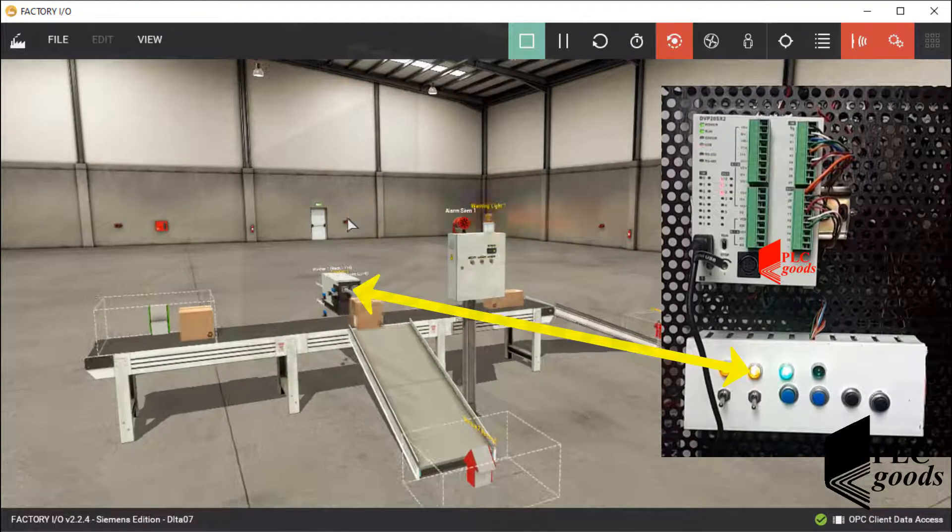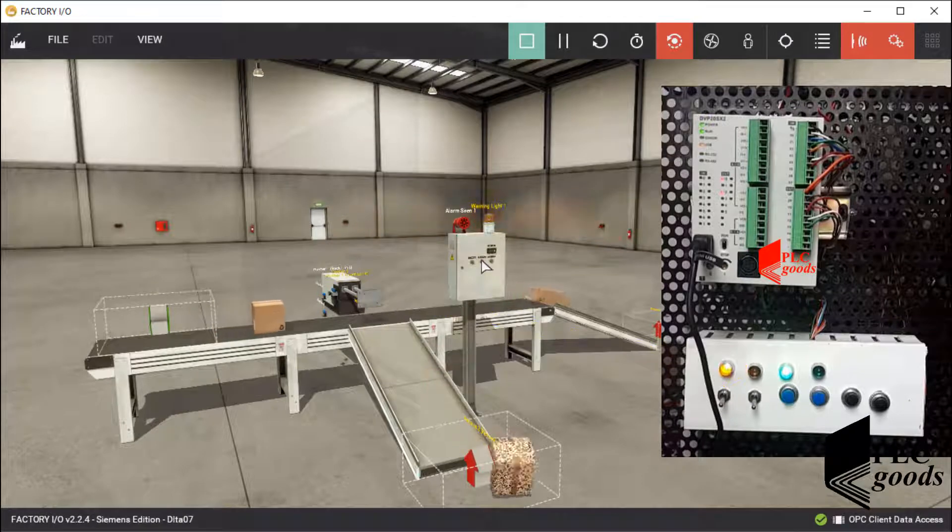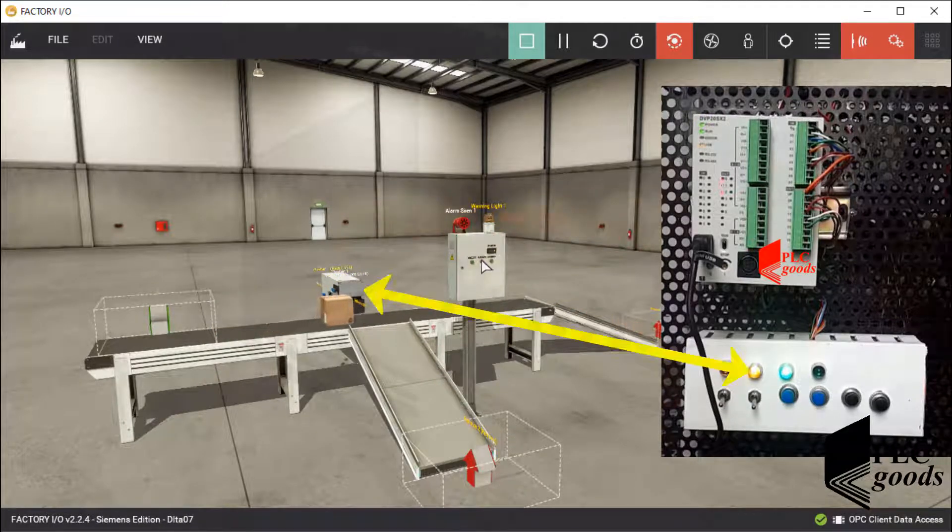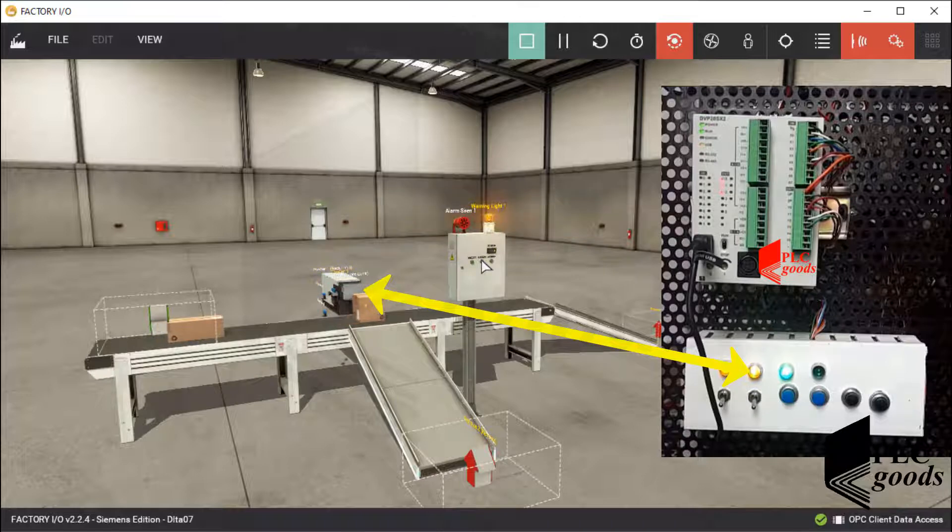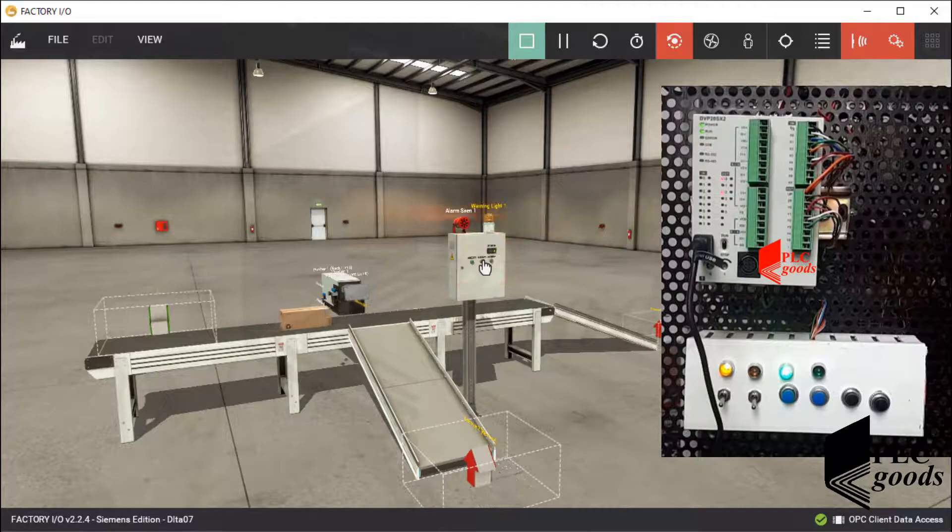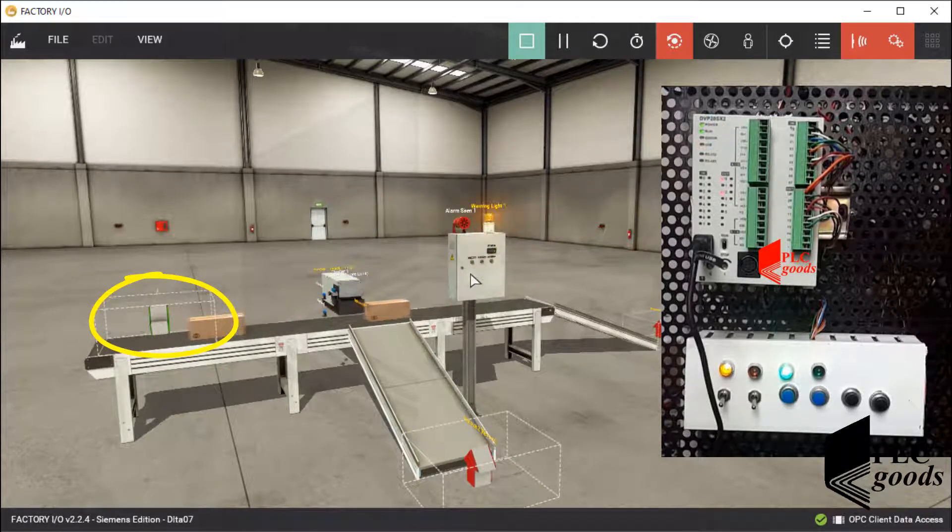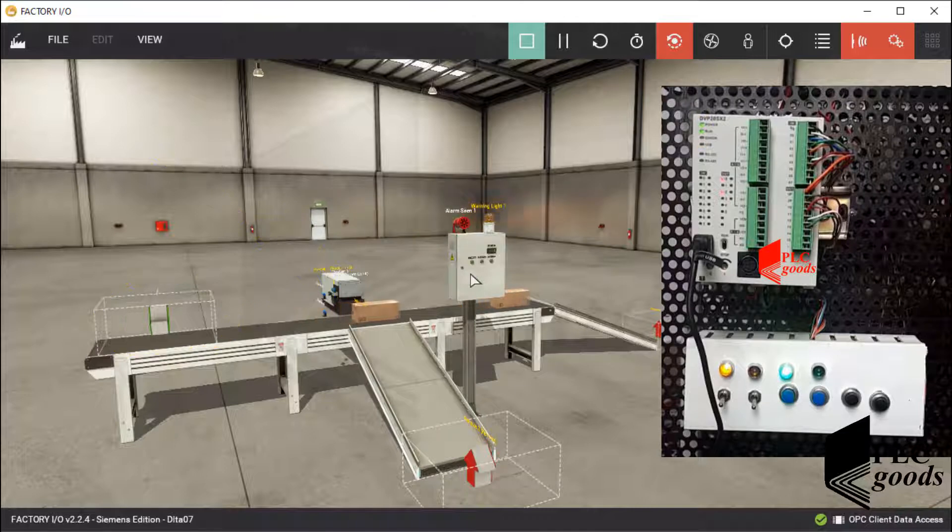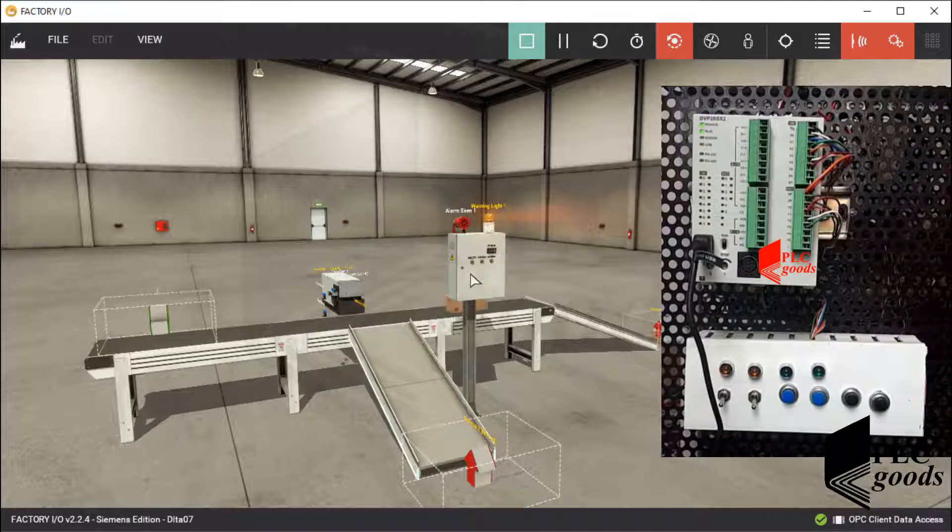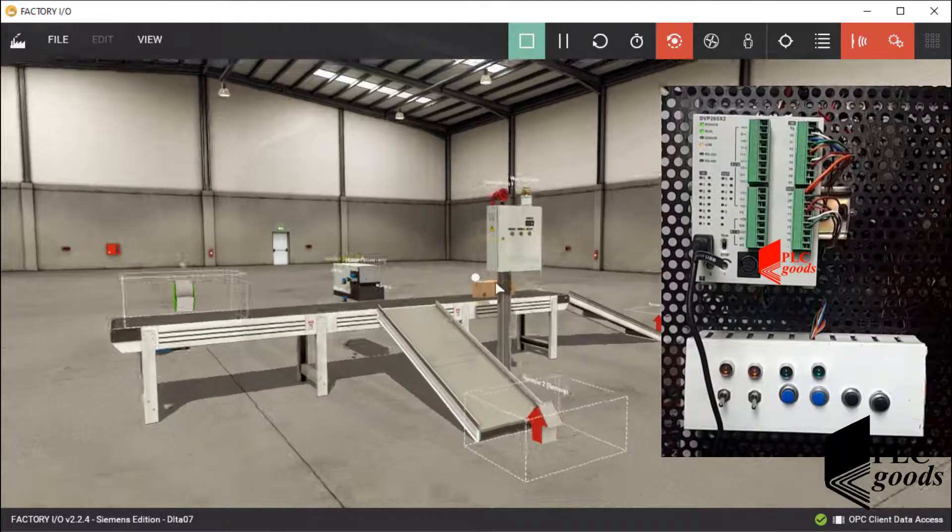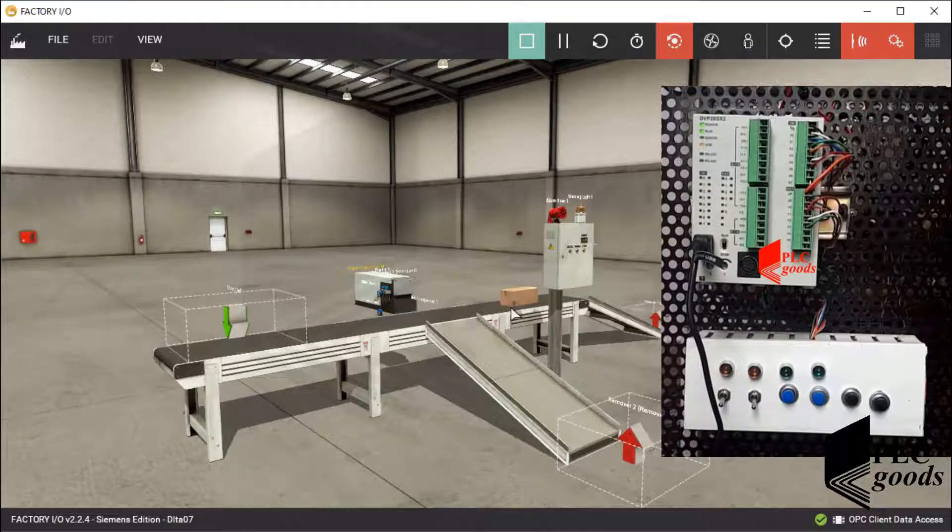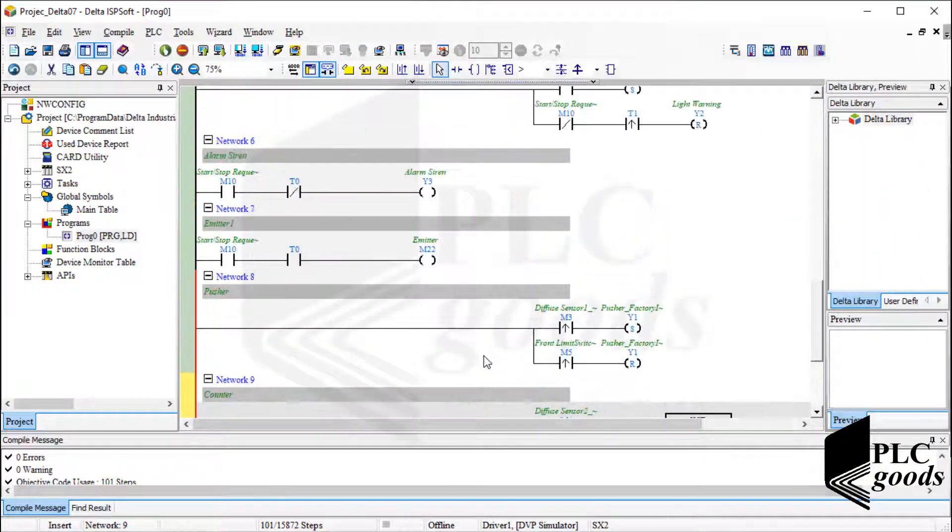I must say a point. Note that there is a little delay between my PLC commands and Factory IO equipment, because of using the OPC server. For example, based on my program, when I press the stop push button, the emitter must be stopped immediately. But as you saw, the emitter hasn't stopped immediately and this box has been inserted. In this simulation, to ensure that there is no box on the belt conveyor, I can increase a timer time in my program from 15 to 20 seconds.